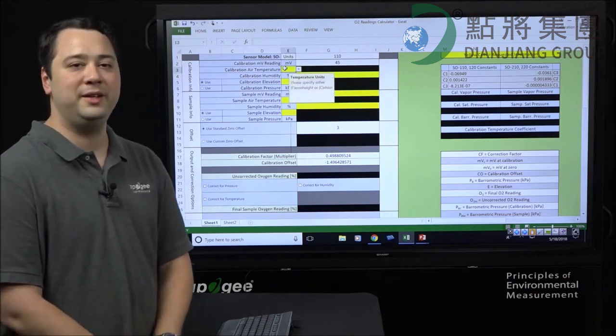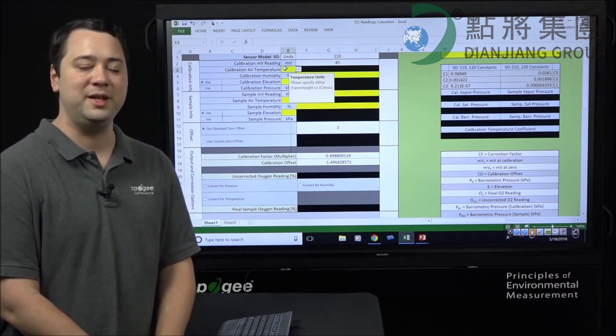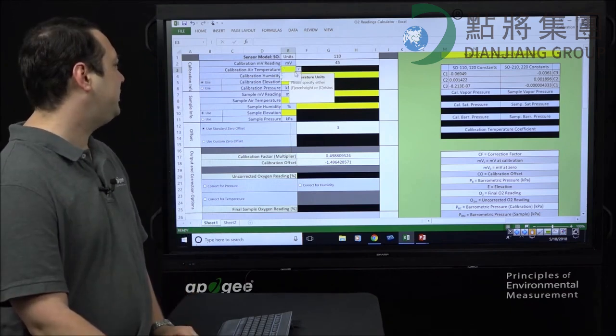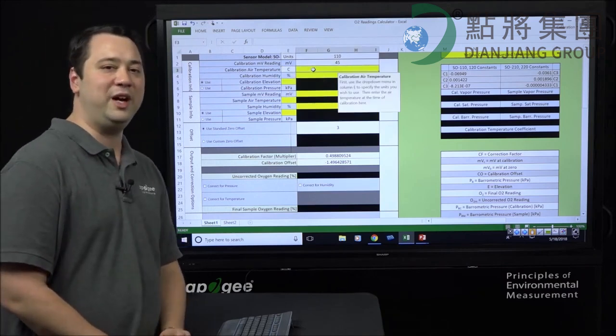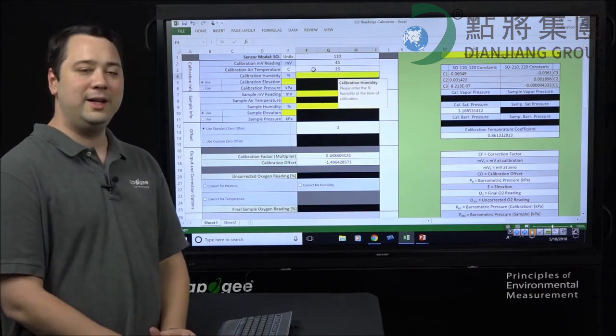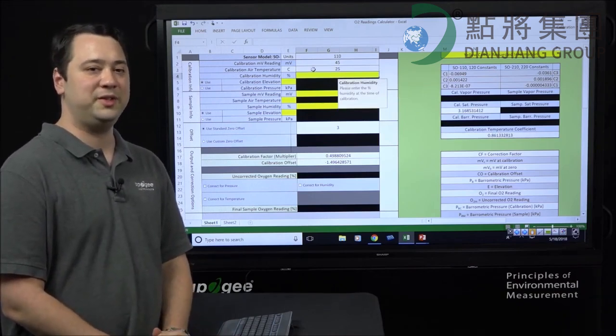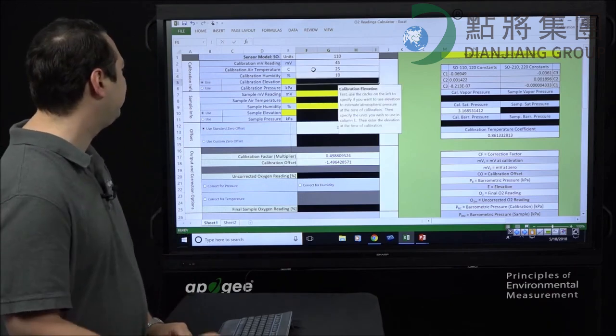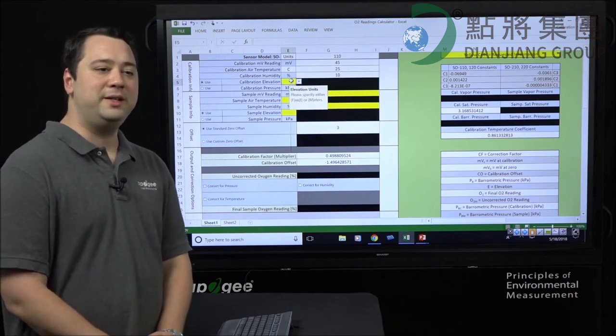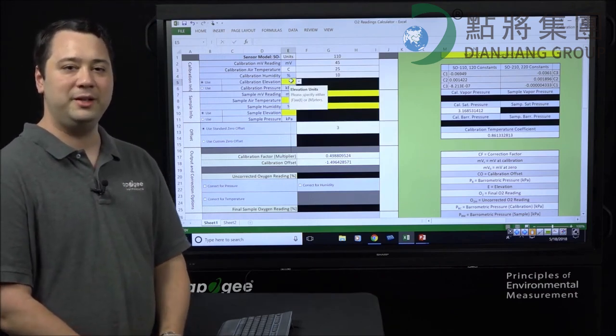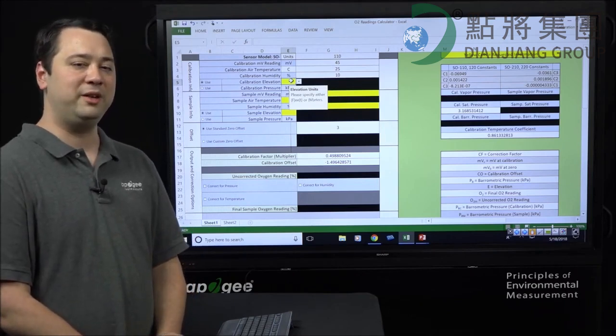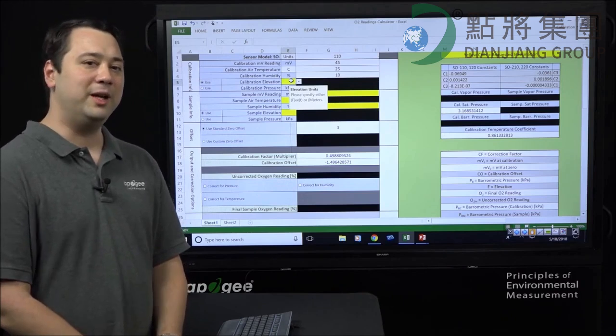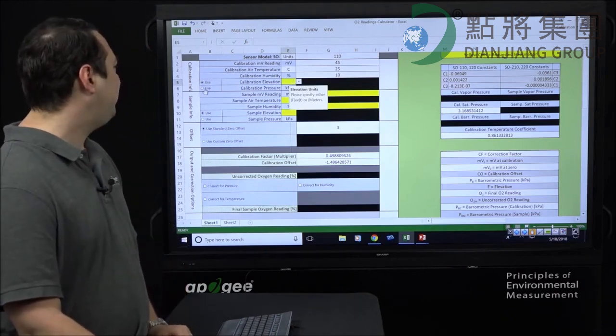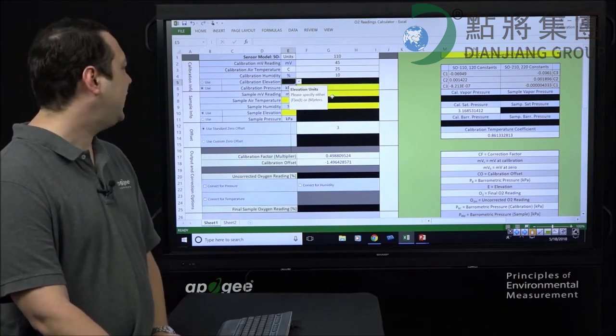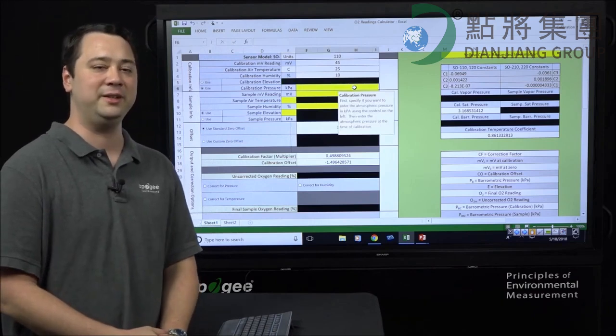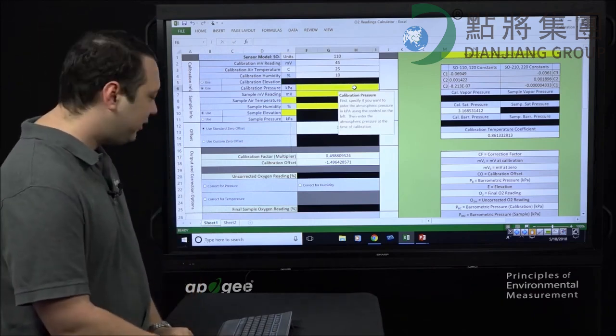So first, you're going to want to enter the environmental conditions for your calibration environment, starting with temperature. So let's select our units for temperature as Celsius, and then let's enter a value of 25 degrees. Now let's say the humidity level in your calibration environment was 10%. So we'll go ahead and punch that in. Next, you'll want to enter either the elevation of your calibration environment in order to estimate the barometric pressure of that environment or enter barometric pressure directly. We'll enter the barometric pressure value by clicking the button on the left here saying Use Calibration Pressure, and we will enter the barometric pressure in kPa of the calibration environment as, let's say, 89.5.